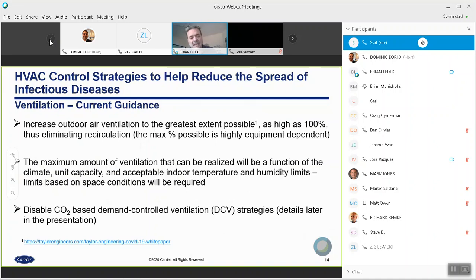They do recommend disabling CO2-based DCV, and I'll talk a little bit more about what we mean by disabling it. DCV strategies normally are designed to reduce the amount of ventilation below the design minimums, and they recommend that you don't do that. Now, again, as I mentioned, there is a lot of debate in the industry about this guidance.